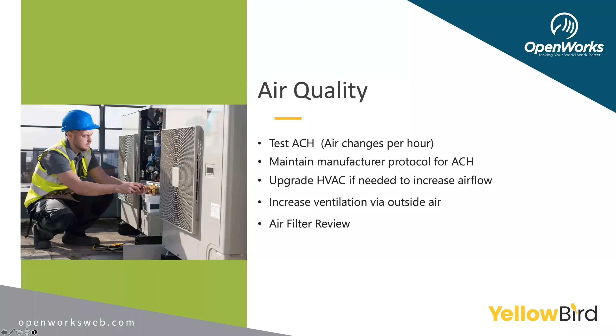A vital part of assessing how well the HVAC system is performing is doing air quality checks. Periodic air quality checks involve checking the airflow, carbon monoxide and carbon dioxide levels, and air changes to see how efficiently you're running your HVAC system, along with humidity levels. All of these tell us how well the system is working. If these levels are out of whack, if there's too much humidity, or the airflow isn't testing at the manufacturer's rate, that could be a precursor for the HVAC system not working properly. So we want those checks in place.